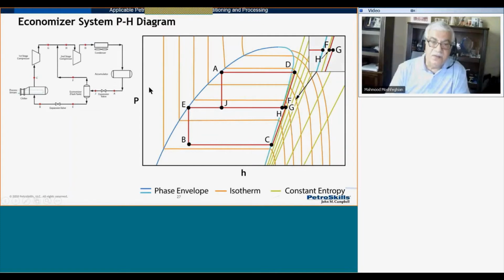So at point A on the process entering the first stage valve, I'm saturated liquid. So I know this condensing temperature, and therefore I draw it. I know the chiller temperature, I draw a horizontal line. But this pressure in the middle, this is the interstage pressure here, which is the same as here, the same as here, same as here as well. Normally, with computer simulation, we determine this so the power for first stage and second stage become equal. If you do that, the total power requirement becomes minimized.